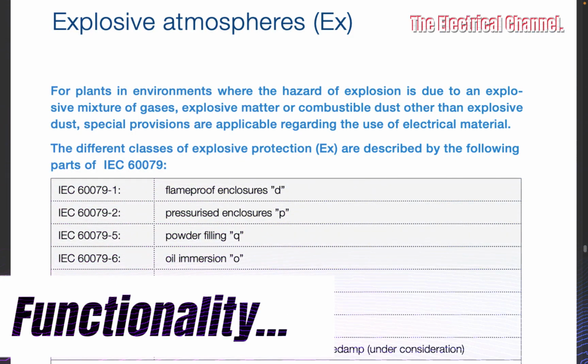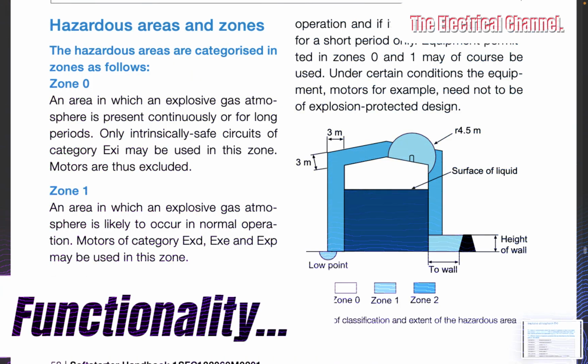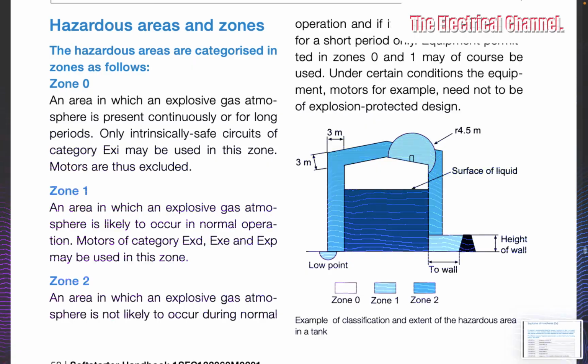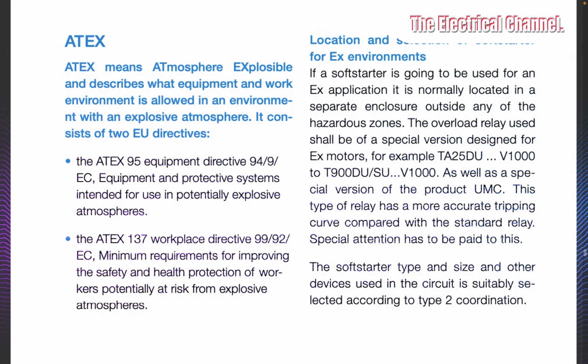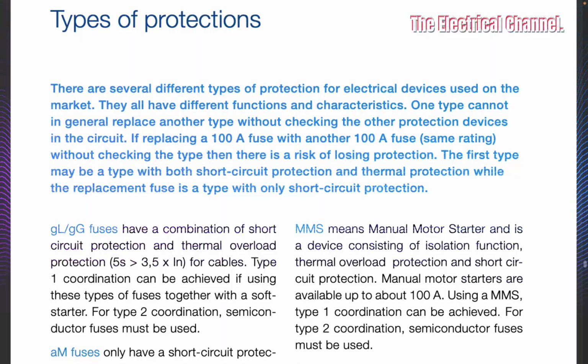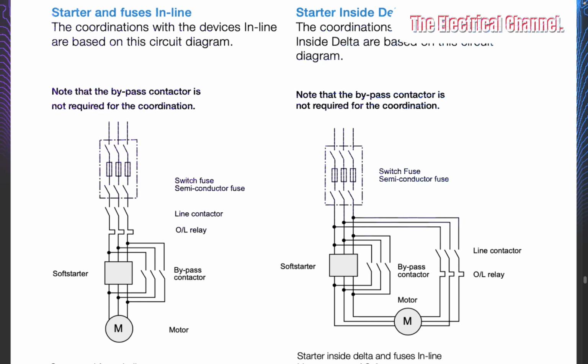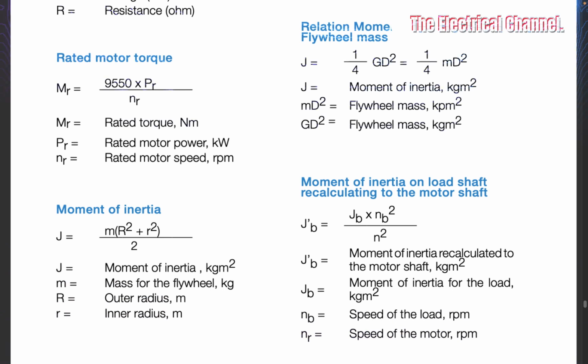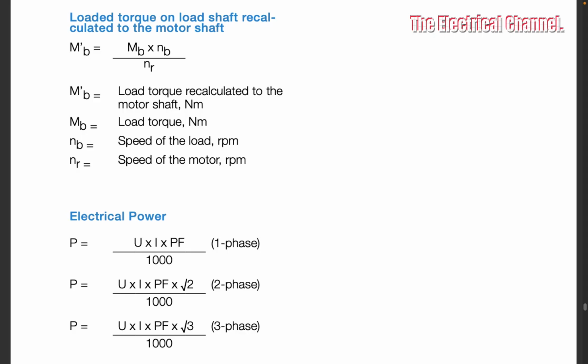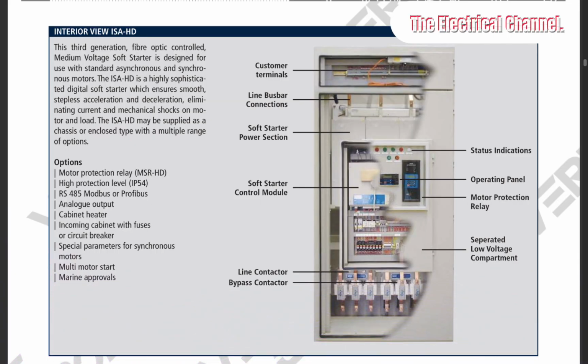Soft starter functionality. A soft starter consists of a number of anti-parallel thyristors, two in each phase. These thyristors are semiconductor components which normally are isolating, but by sending a firing signal, they can start to conduct, allowing the voltage and current to pass through. When performing a soft start, the firing signal is sent to the thyristors so that only the last part of each half period of the voltage sine curve passes through.